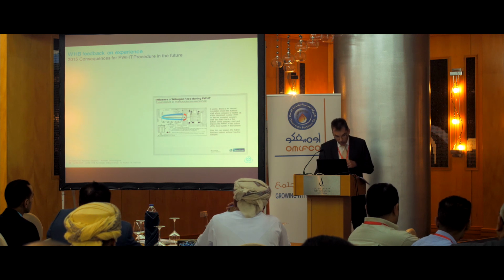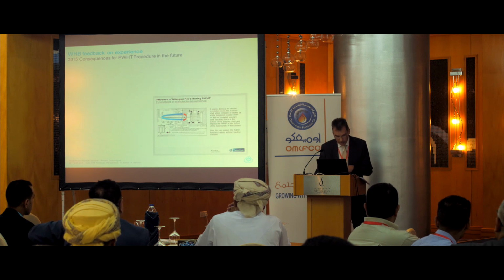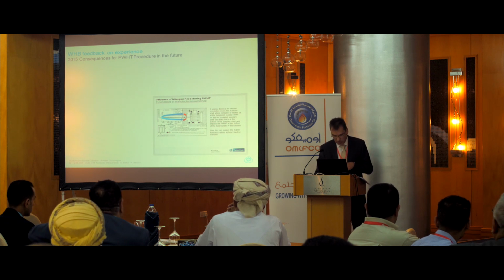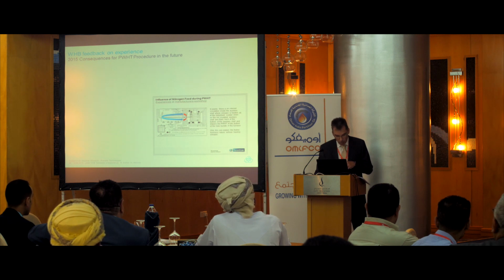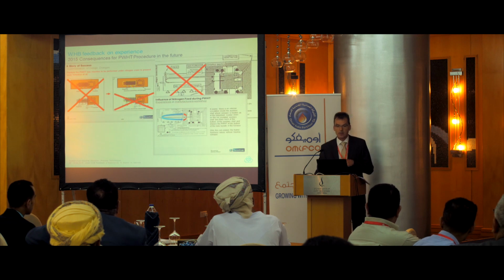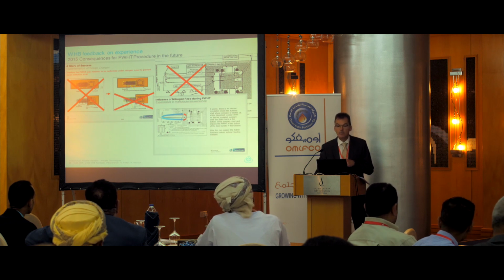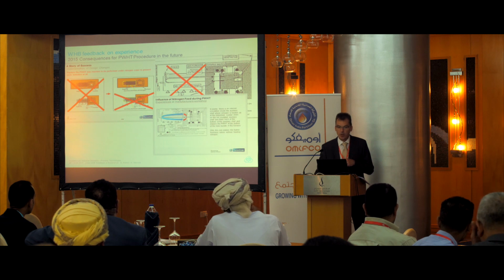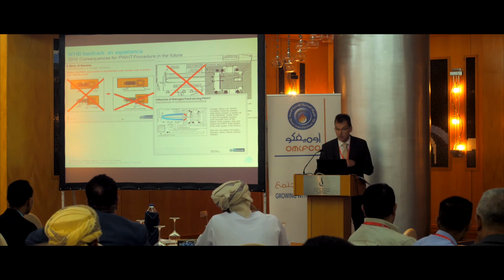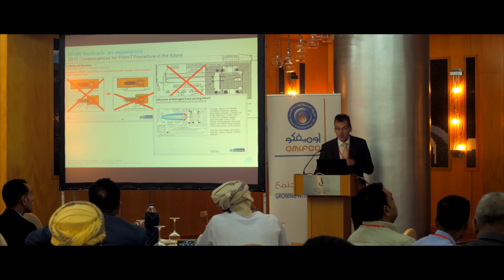In order to avoid any influence by thermal circulation inside the auxiliary shell, when it is partly inside and outside of the furnace, it was decided that from now on it is only accepted to have the auxiliary shell completely inside the furnace. That means in the early stages, in the 80s, the 90s, and 2000, it was possible to do heat treatment if the manufacturer had a big furnace, with the complete waste heat boiler inside the furnace, without auxiliary shell, without nitrogen. That was the first. Then we had furnaces with only part of it inside. This was forbidden before 2006, 2007.